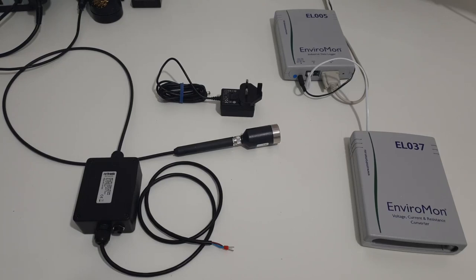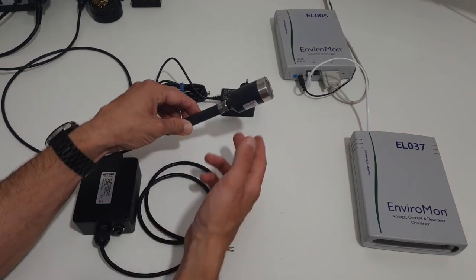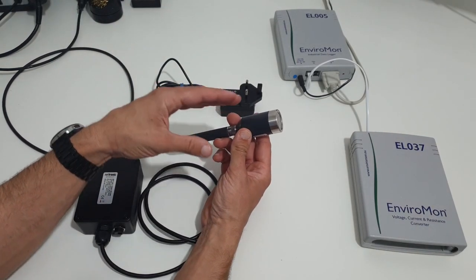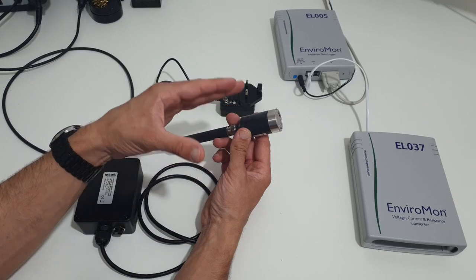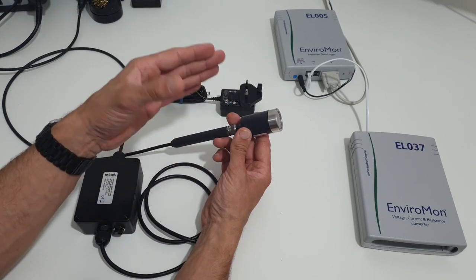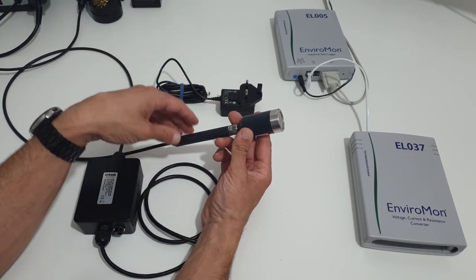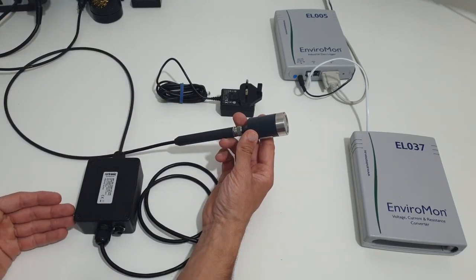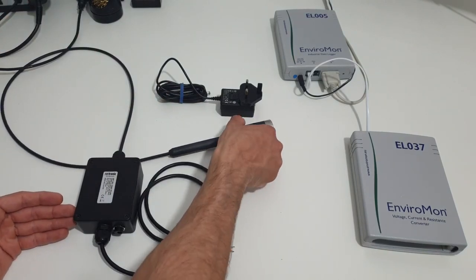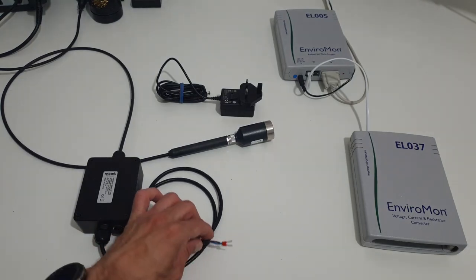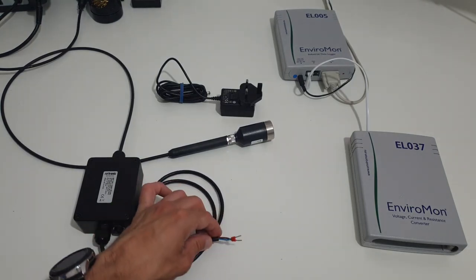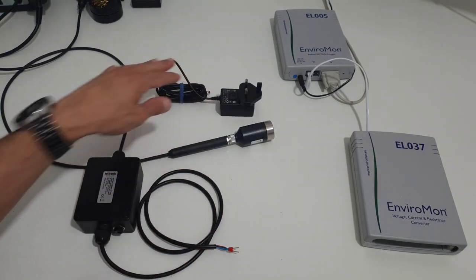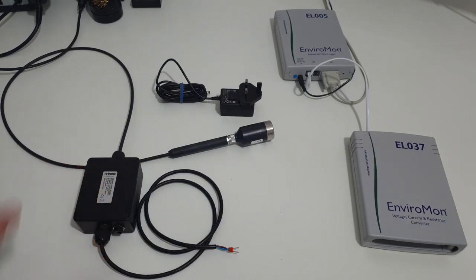So the probe that we have here can measure a range of 0 to 2% CO2. So if we were to look at the probe itself at the top here, we see the head of the probe, which has the chamber with a light source and the optical filter, which then connects to a signal conditioning box, which converts the signal to a 4 to 20 milliamp signal, which is then fed into the data logger. And it also comes with a power supply which powers the circuitry of the signal conditioning box.